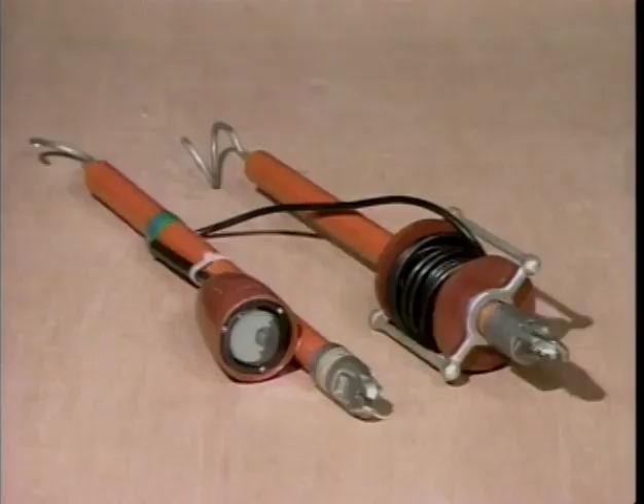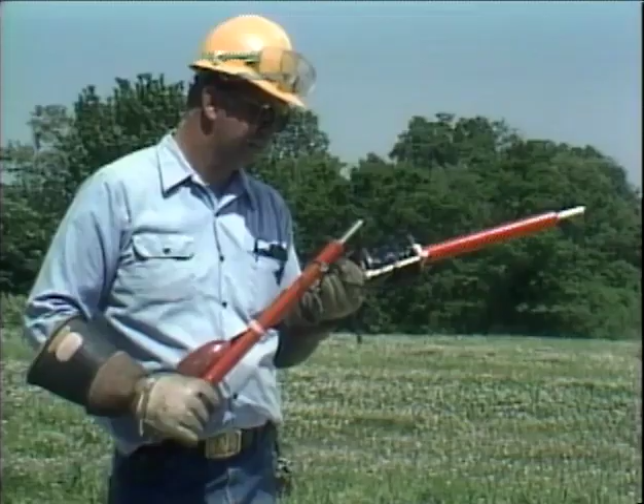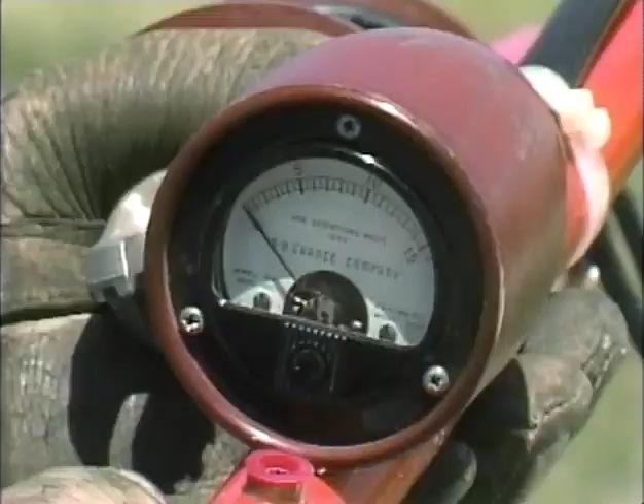Every tester has a safe operating range, requires routine inspections, and must be used properly to get accurate test results. For example, this phasing test set has a safe operating range from 0 to 16,000 volts. If you used this tester on an energized circuit that exceeded this range, you could damage the tester, or worse, get a false indication of the absence of voltage on a circuit. Now, in this situation, assuming the circuit is dead could place you in danger when you work on the circuit. So before you use a tester, make sure the circuit you're testing is within the correct operating range of the device. Now, you also need to inspect the tester both before and after you use it to make sure it's in good working condition. If a tester is damaged, it could give you an inaccurate reading.